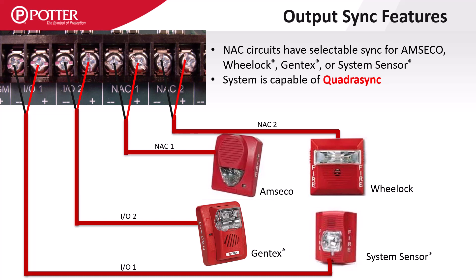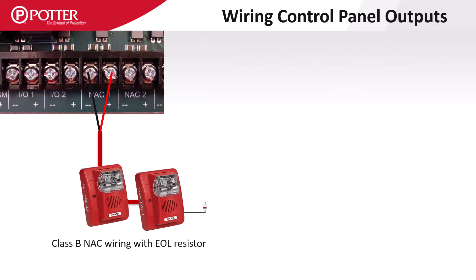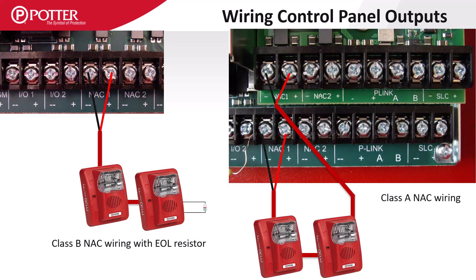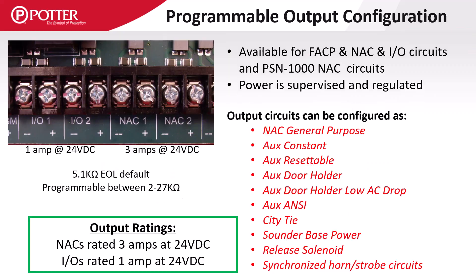The four strobe protocols supported are Amseco, Wheelock, System Sensor, and Gentex. Control panel output circuits can either be wired class B with an end-of-line resistor or in class A when using a class A card. In the Potter programming software, all panel NAC and I.O. circuits as well as PSN1000 NAC circuits can be set to provide the following functions.